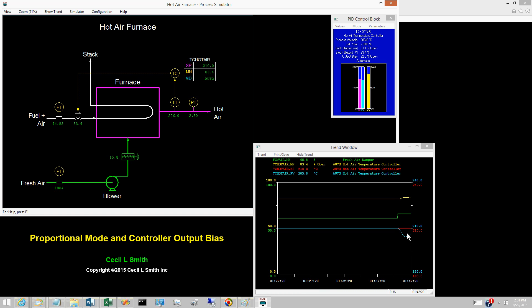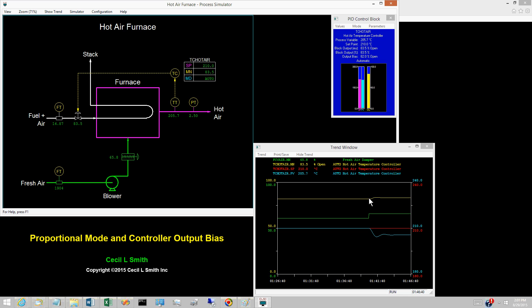The hot air temperature is said to droop down, and eventually lines out at 205.7 degrees Celsius. The hot air temperature controller has increased the controller output from 82% open to 83.5% open.